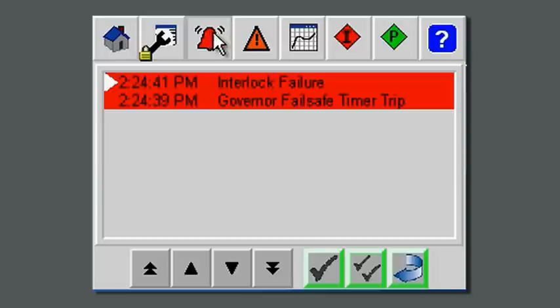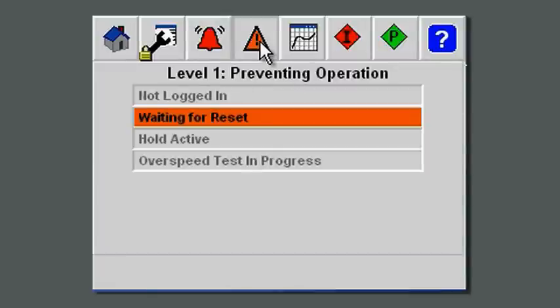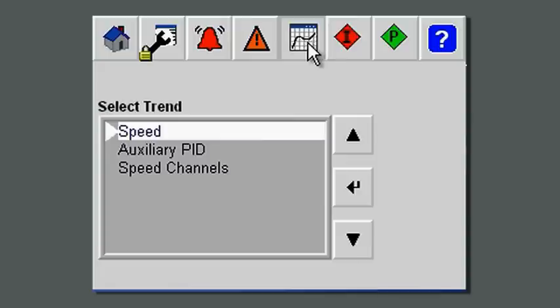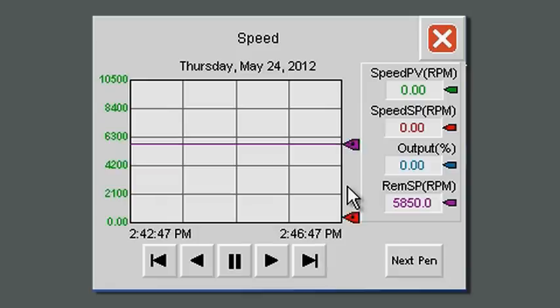The page with the triangle shows the warnings. These display particular warnings or anything that's going to be preventing you from starting the turbine. In this instance, it's waiting for a reset from the operator before it will allow the turbine to be restarted. The trend screens allow you to pull up individual trends of some of the analog data — in this case, the speed PID. This will show you all the information about that particular PID. These trends are not meant to be historical; they're 5 or 10 minutes in length, but they're very useful for doing loop tuning on the particular PID you're working with.